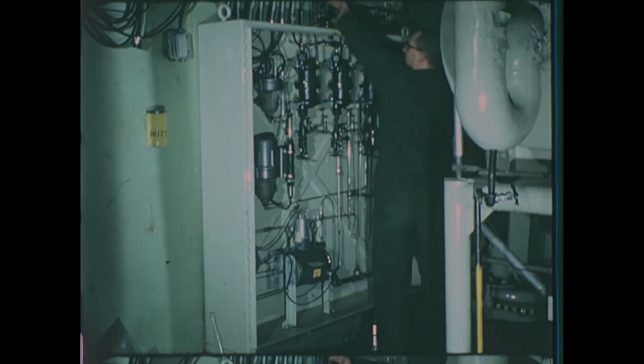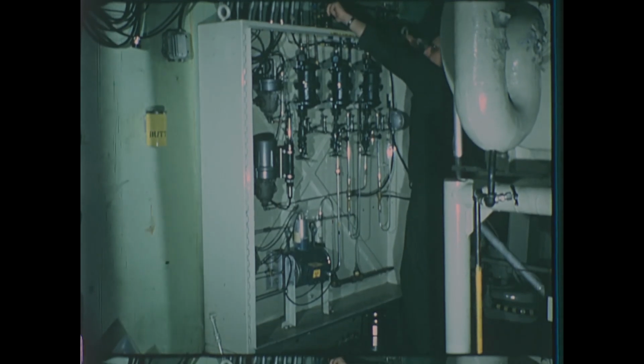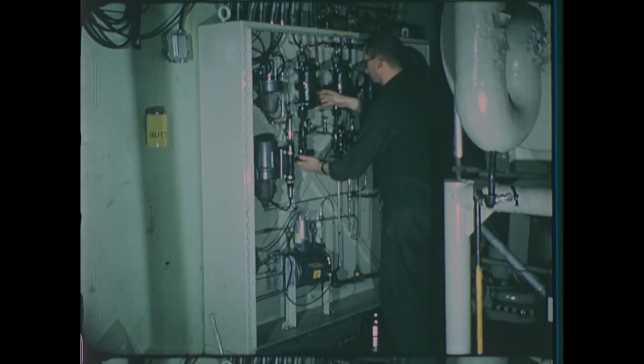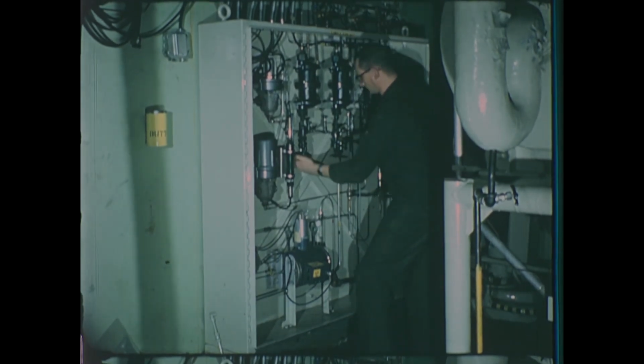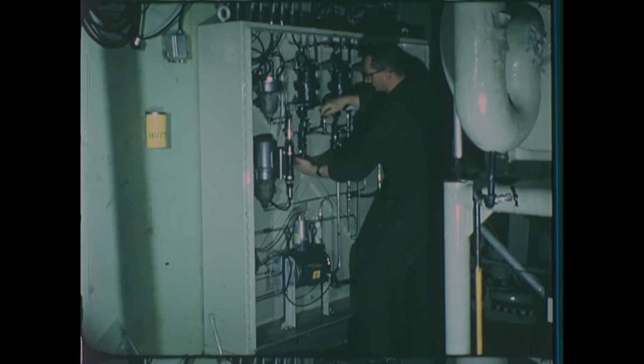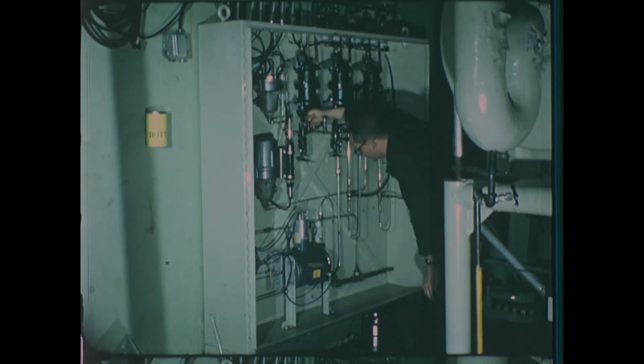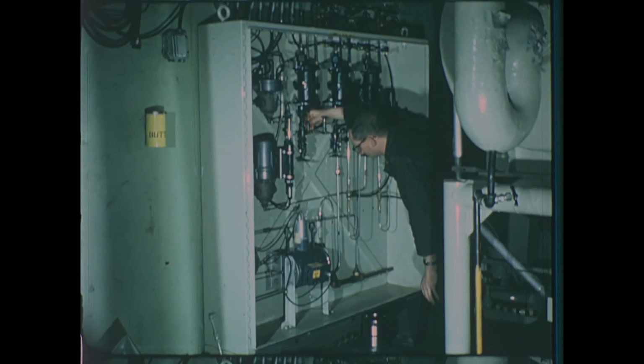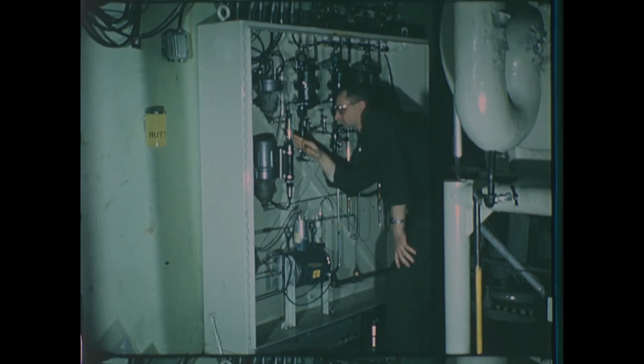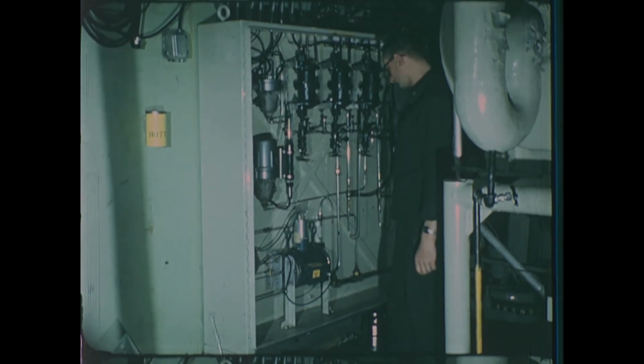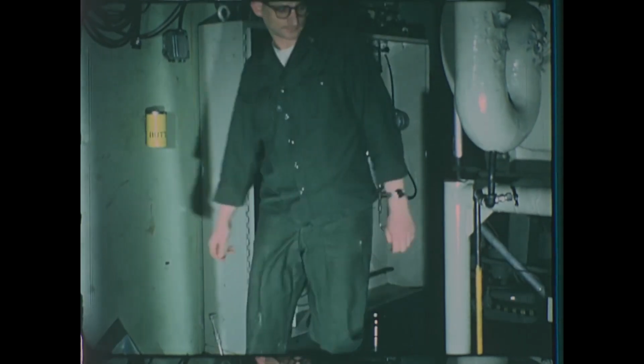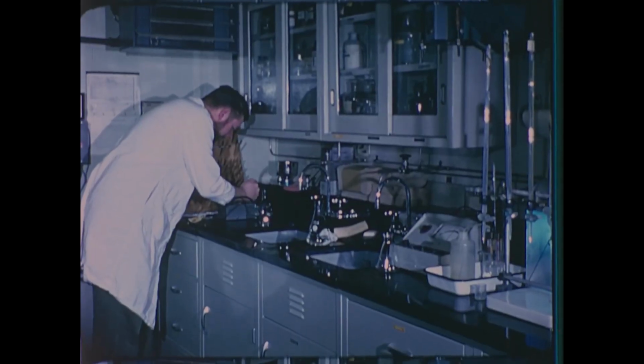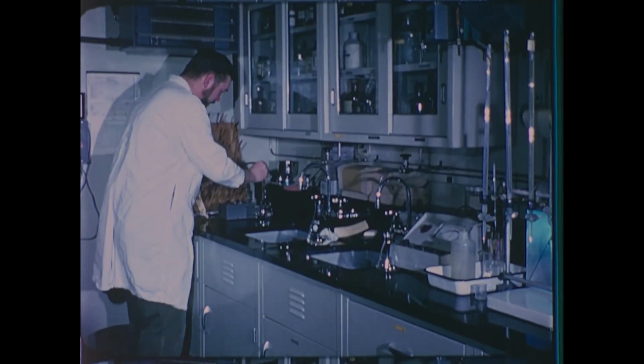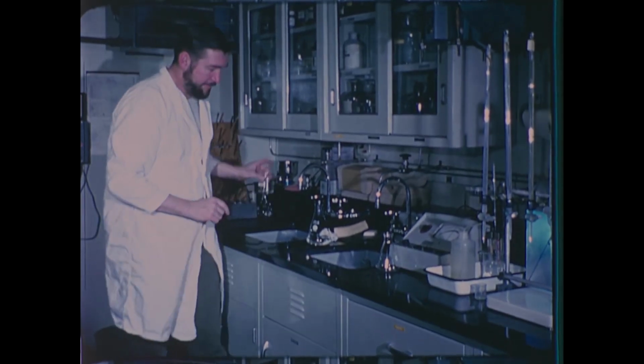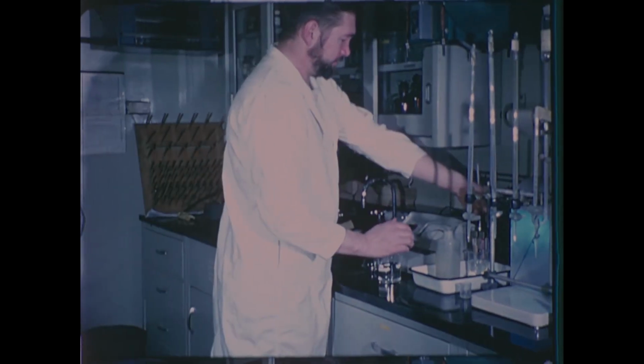During the day-by-day, watch-by-watch operation of the PM3A nuclear power plant, there are many steps of routine maintenance. An equipment operator checks the temperature and rate of steam generator blowdown. Daily, process control personnel will analyze water samples. These samples, taken from feedwater, condensate, blowdown, and makeup systems, are checked for chemical purity and radioactivity.